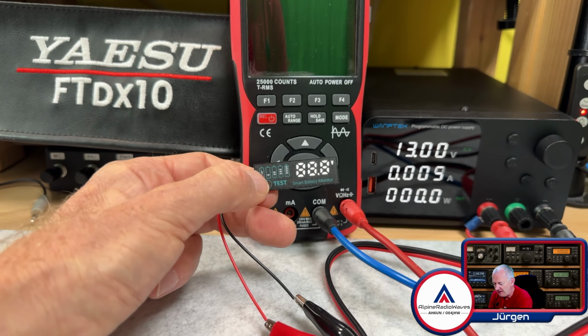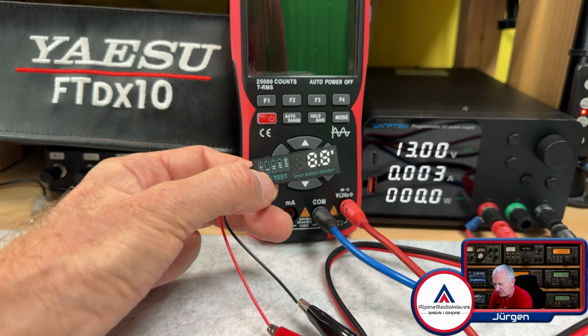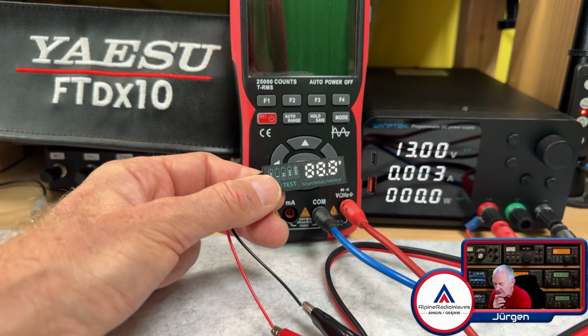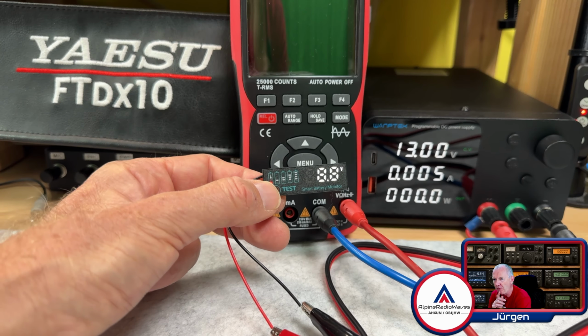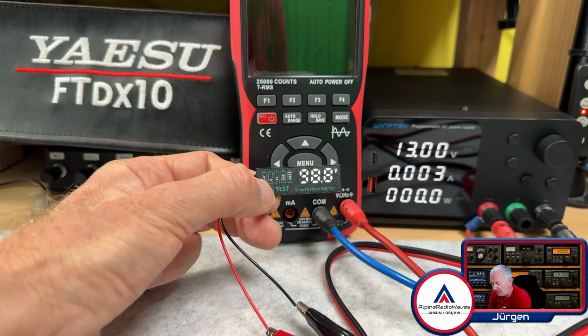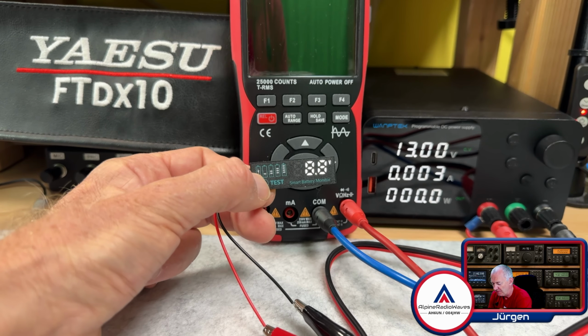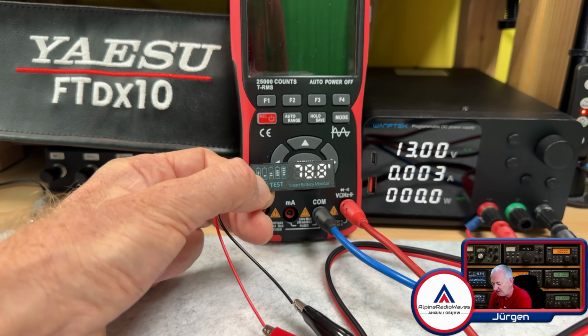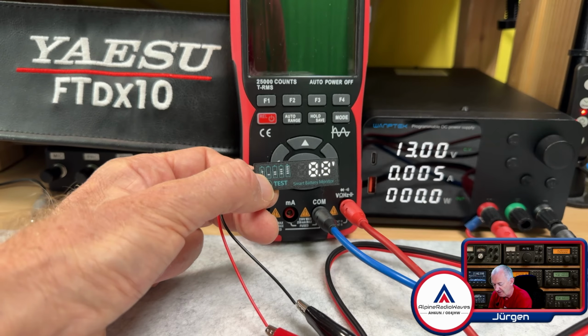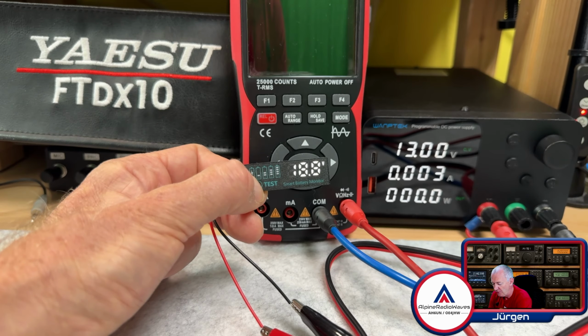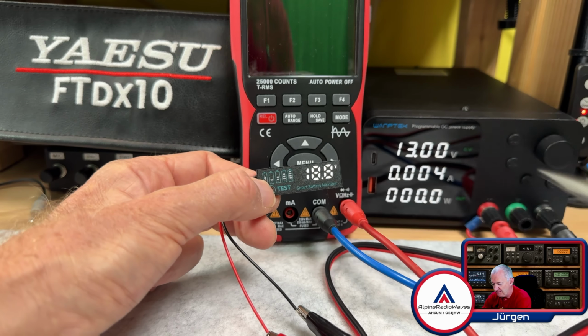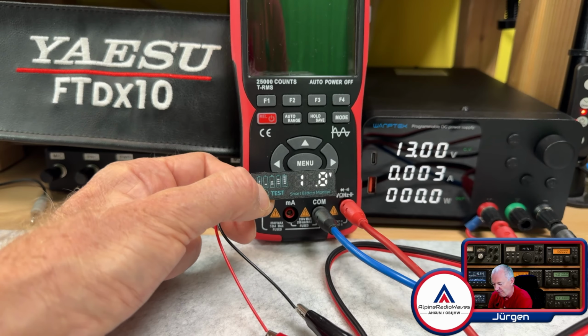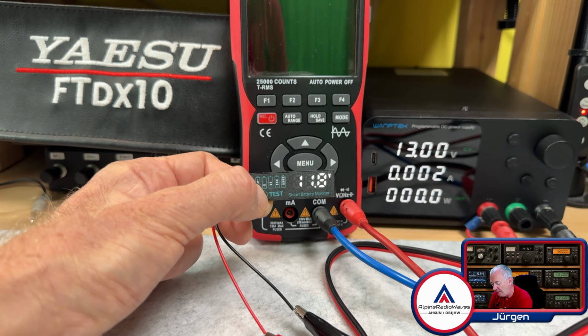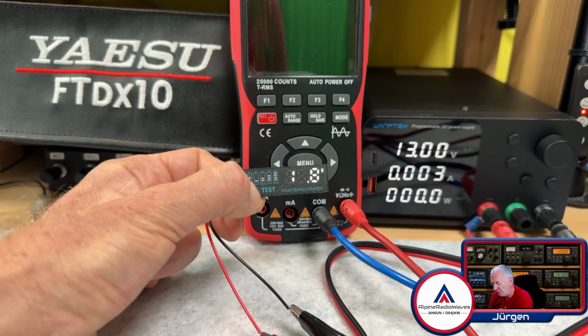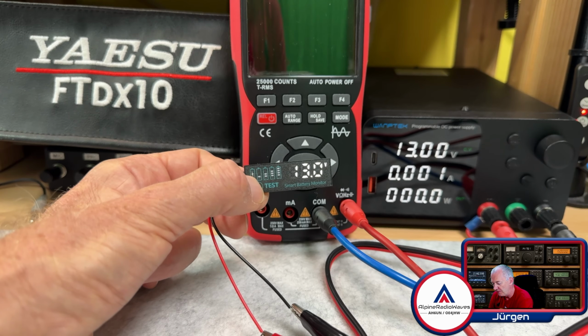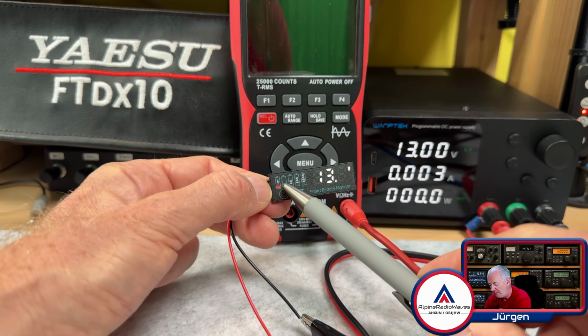And now you can set the low voltage. Let's say I want to have 10% state of charge at 13 volts. Click through the digits: 1, then press and hold, now the second digit blinks. 13, click one more time till it says 3. Press and hold, and now I set this to 0. So that's now the lower limit here, 13 volts.